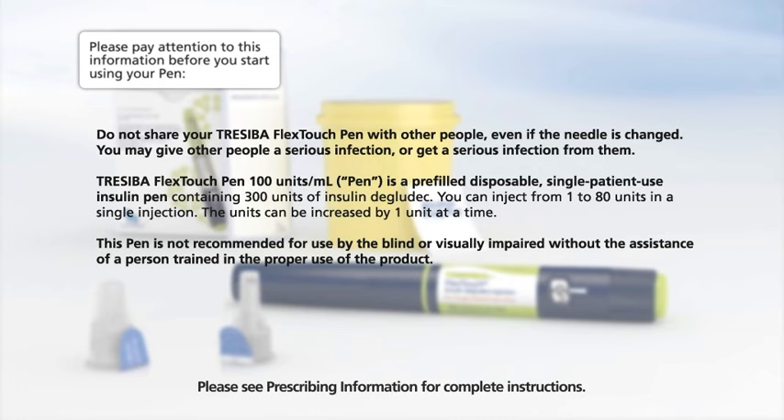TRESIBA FlexTouch Pen 100 units per milliliter, generally referred to as just pen in this video, is a pre-filled, disposable, single-patient-use insulin pen containing 300 units of insulin degludec. You can inject from 1 to 80 units in a single injection. The units can be increased by one unit at a time. This pen is not recommended for use by the blind or visually impaired without the assistance of a person trained in the proper use of the product.